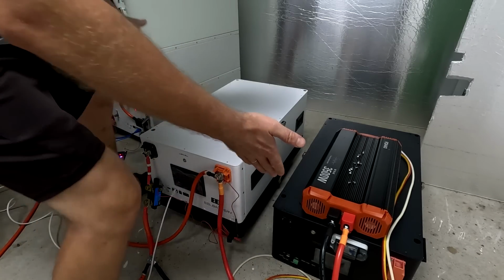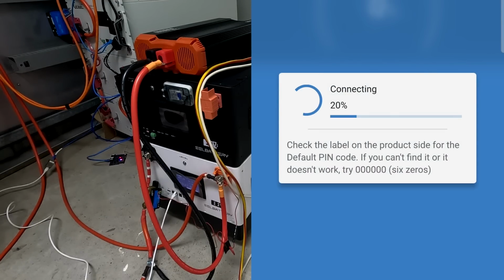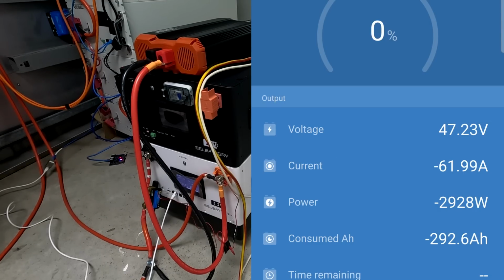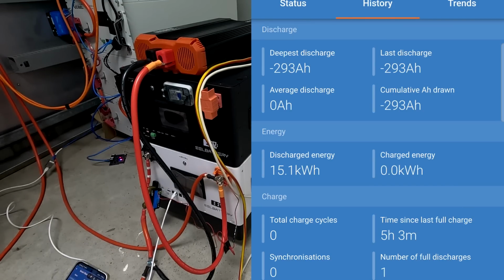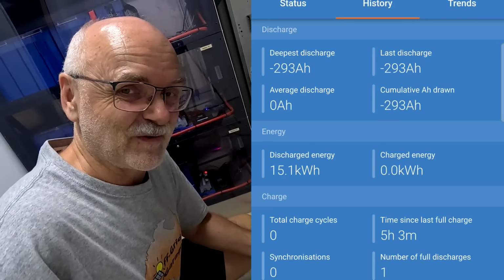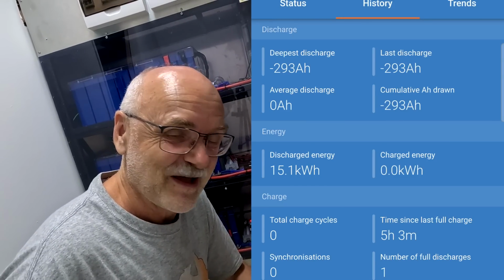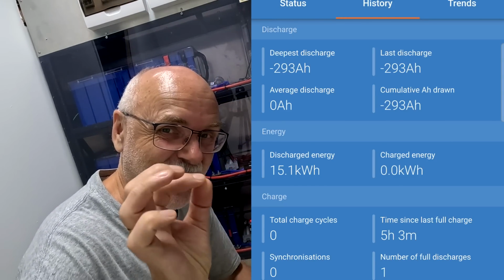That's crazy. So we have just a low voltage warning on the Phoenix inverter as well. The smart shunt shows already 0% state of charge. We are under 48 volt, and we are actually under 47 very soon. Putting out 63 amps, and we have discharged 293 amp hours. That is 15.1 kilowatt hours from an LF280K.